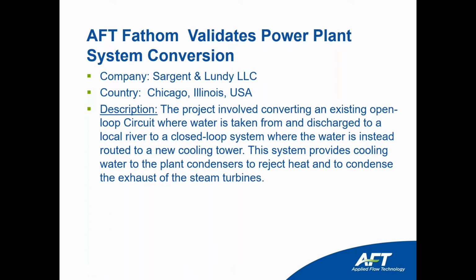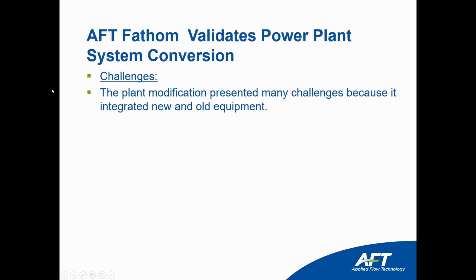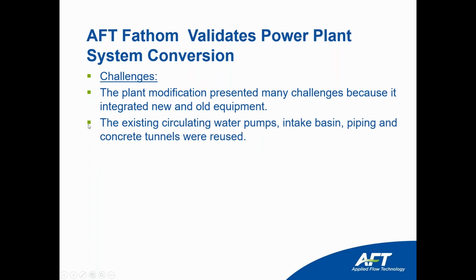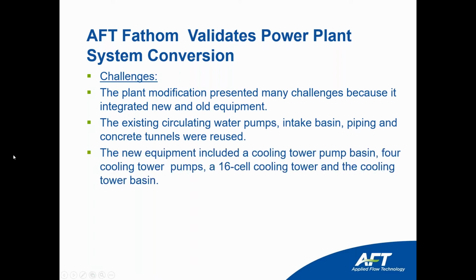So the description: the project involved converting an existing open loop circuit where water is taken from and discharged to a local river to a closed loop system where the water instead is routed to a new cooling tower. This system provides cooling water to the plant condensers to reject heat and condense the exhaust of the steam turbines.